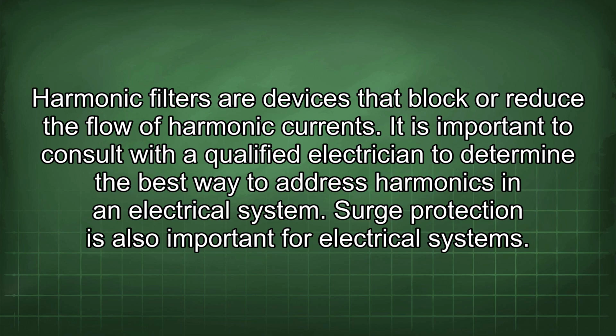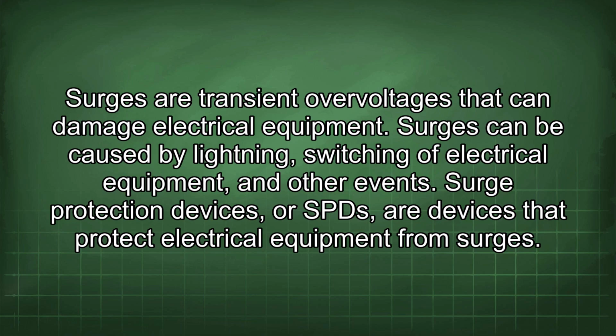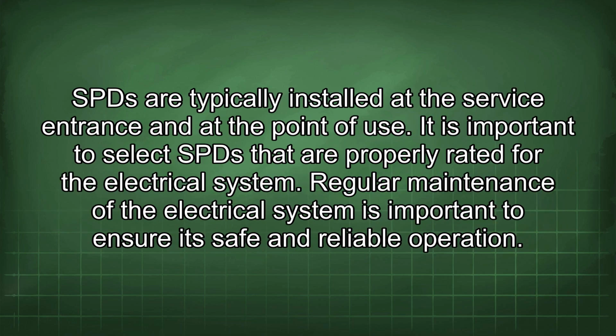system. Surge protection is also important for electrical systems. Surges are transient overvoltages that can damage electrical equipment. Surges can be caused by lightning, switching of electrical equipment, and other events. Surge protection devices, or SPDs, are devices that protect electrical equipment from surges. SPDs are typically installed at the service entrance and at the point of use. It is important to select SPDs that are properly rated for the electrical system.